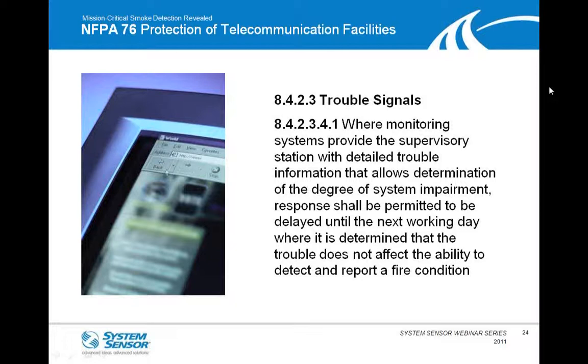for a trouble condition, rather than have to race out and address it at that immediate instance, as long as the device or the system gives good discrete information as to what is going on with the system, if it's not jeopardizing its ability to detect smoke or fire and report the fire condition, it can be delayed until that next working day.